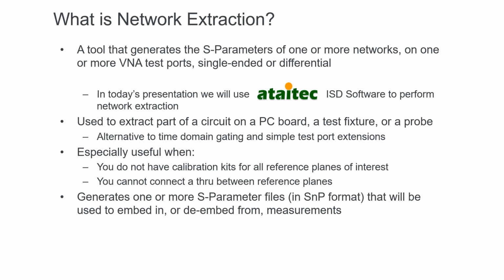So first of all, what is network extraction? Well, network extraction is a tool that we use to generate the S parameters or the model for some network that we want to then embed or de-embed later from a VNA test port. This model can be single-ended or differential. And as I said earlier, in today's presentation, we're going to use the Ataitec ISD software to perform this network extraction, in our example being a differential probe.